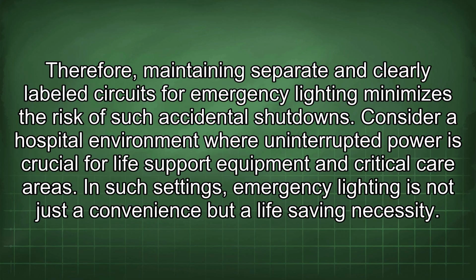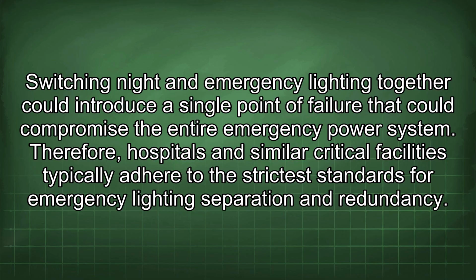Consider a hospital environment where uninterrupted power is crucial for life support equipment and critical care areas. In such settings, emergency lighting is not just a convenience but a life-saving necessity. Switching night and emergency lighting together could introduce a single point of failure that could compromise the entire emergency power system. Therefore, hospitals and similar critical facilities typically adhere to the strictest standards for emergency lighting separation and redundancy.